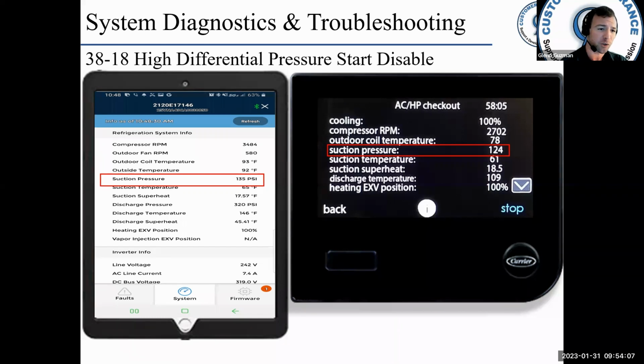So the first thing you want to do is connect your low and high side gauges and then look at the UI, look at the app and see what my pressures show on here and what I am actually seeing on my gauges. Okay. The fault will clear and the unit will start normally once the pressure differential is below 100 PSI and the demand is present. So if the unit is off, in a standby mode, and your suction reads 100 and your discharge reads 250, it's not going to start. The differential between those two is about 150 PSI. So that's what it's telling you, high differential pressure start disable.